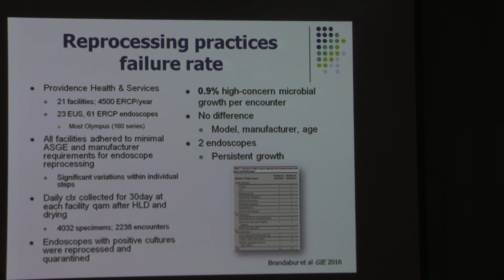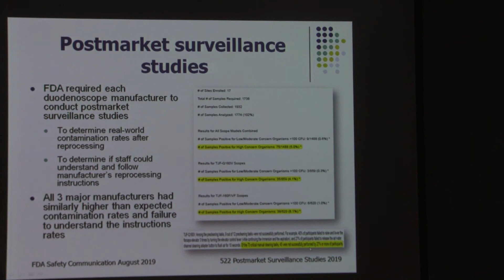However, more recently this year, the results came from FDA post-marketing surveillance studies that the FDA actually required each duodenoscope manufacturer to conduct, to determine the real-world contamination rate, and also look at whether the staff is able to understand and follow manufacturer processing instructions. And unfortunately, all three manufacturers had similarly higher than expected contamination rates and failure to understand the instruction rate. In particular, here the rates of high concern organisms, 5%, and then more than half the time, staff was not able to perform critical tasks or follow the instruction.